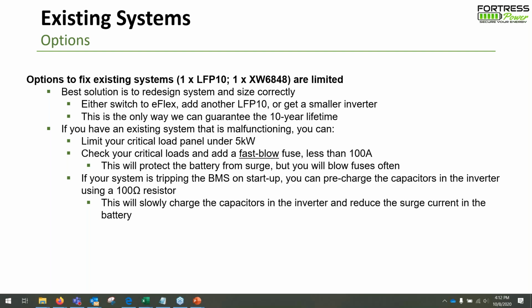We can also check your critical loads and add a fast blow fuse that's less than 100 amps. So let's say your total amperage in your house is 30 amps. You can add a 50 or 60 or 70 amp fuse, and that way we can be sure that you'll never pull more than 100 amps. So this will protect the battery from surge, but you will blow the fuses pretty often. You will have to replace these fuses, but it's cheaper than having to fix the batteries. If your system is tripping the BMS on startup, you can pre-charge the capacitors in the inverter using a 100 ohm resistor. So this will slowly charge the capacitors in the inverter and reduce the surge current in the battery.